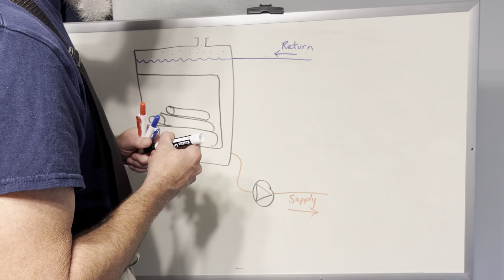So this is a vented system, so this is going to apply to a vented system. One reason - first of all, whatever your boiler manufacturer tells you to do, if they say pipe it from down here and run that way and return back to the top, do that. If they say pull from the top, going this way, and return back to the bottom with your pump up here pushing that way, do that.